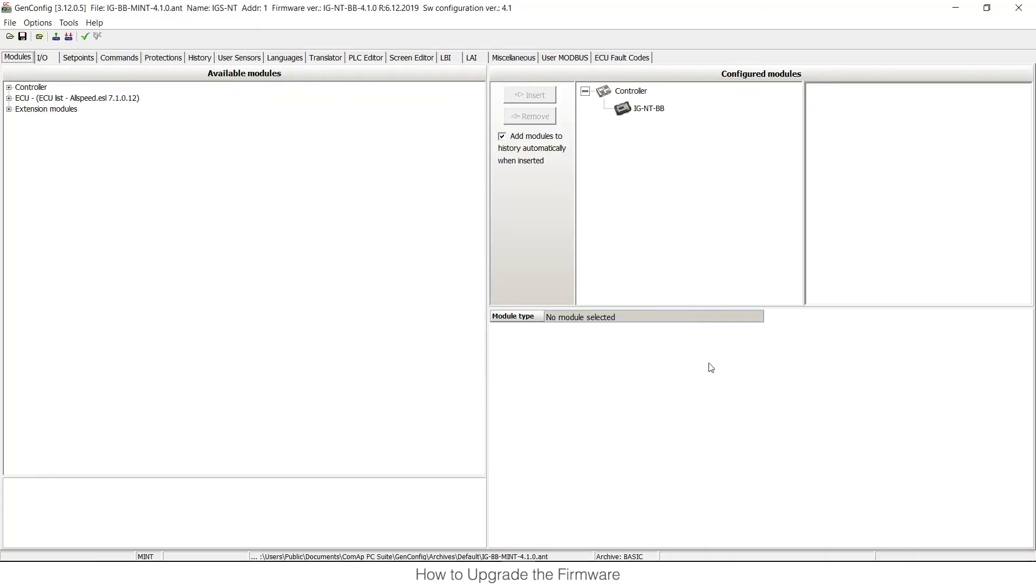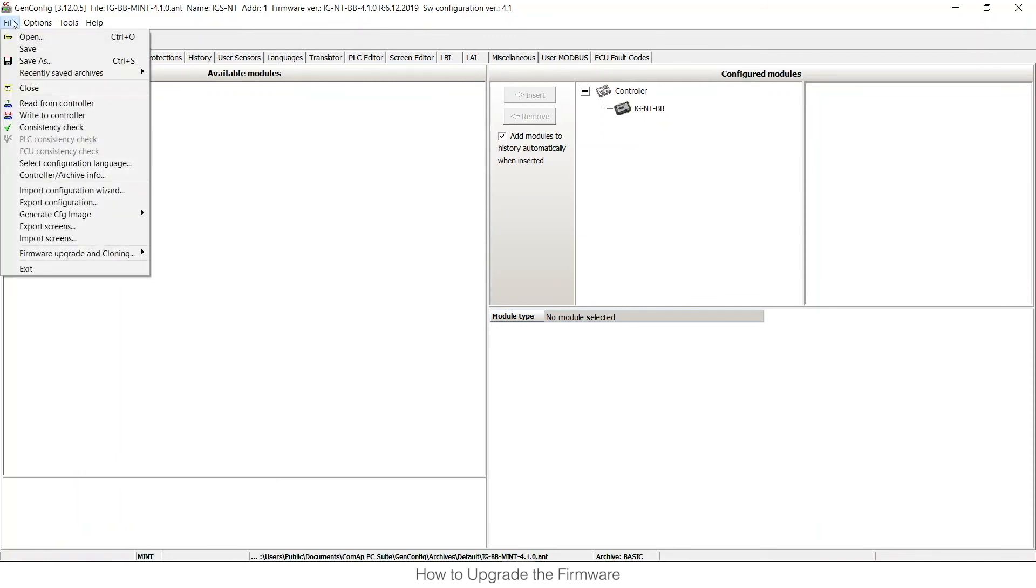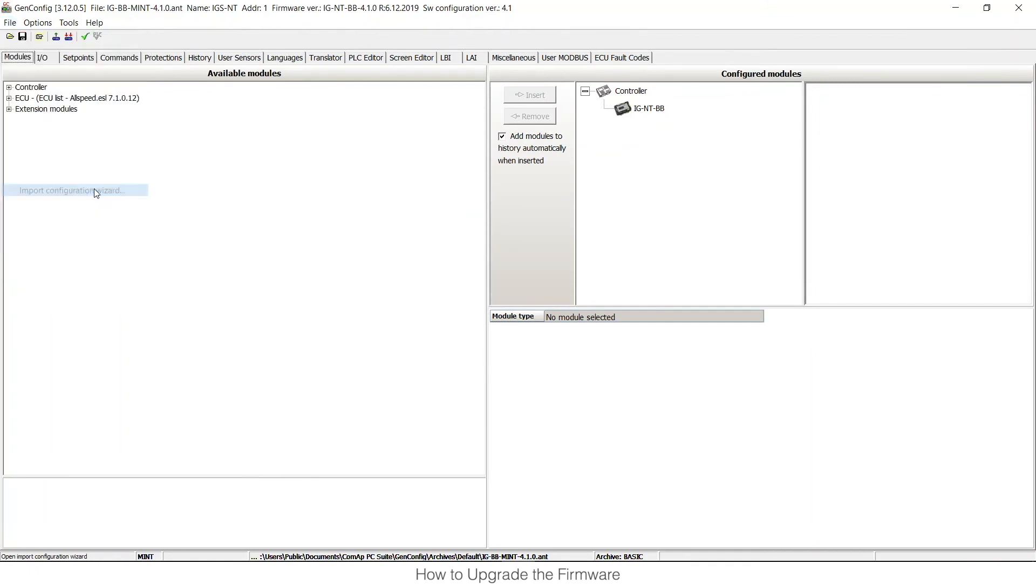Now we have an archive with default configuration and Mint application and as a next step we need to import the original configuration, which means import inputs and outputs and set points and we can do that by clicking File, Import Configuration Wizard.